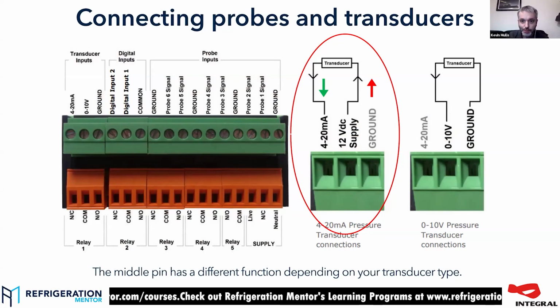So on this one, we can see I've marked up that plug where it's circled with how the transducer works with their wiring. So you can buy a transducer for any given range you might want, like a 20 bar range one for suctions on HFC plant. You can buy 65 bar range one for CO2 suctions. You can buy 125 bar range for high pressure stuff. They all connect the same way. So when you buy your RDM transducer, it's got a cable with it. It's got a red and a green wire and a little thin black wire. Little thin black wire doesn't get used. Red and green get used, and I've marked in red and green there how that goes in.